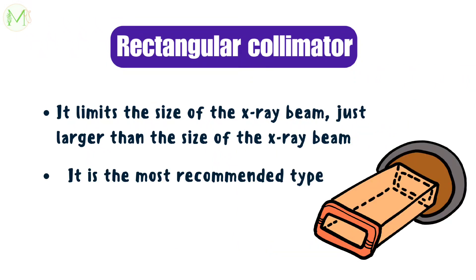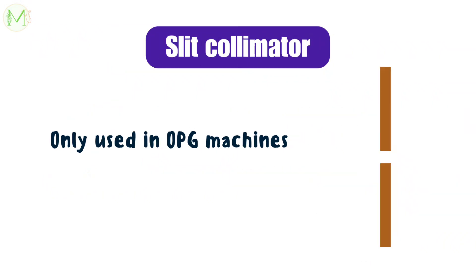The next type of collimator is rectangular. It limits the size of the X-ray beam to just larger than the size of the X-ray film, and it is the most recommended type of collimator. Lastly, we have the slit type of collimator, which is used only in OPG machines.